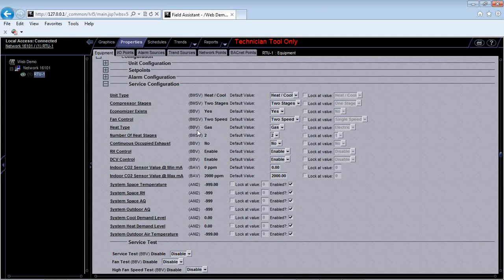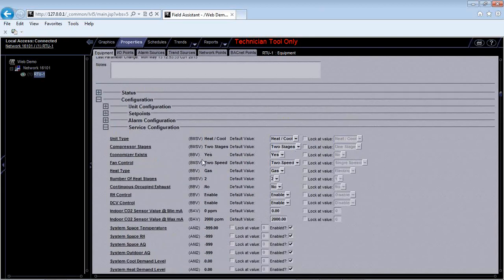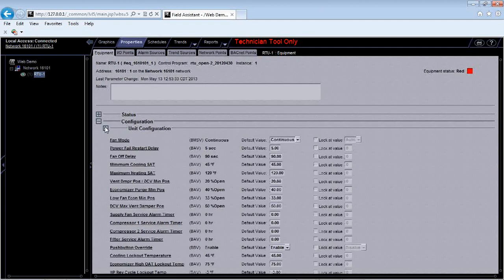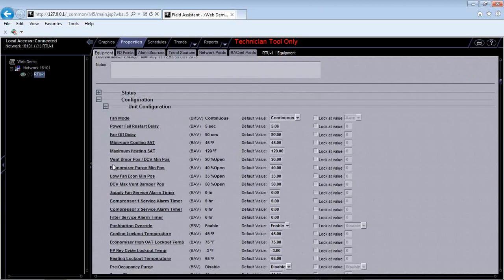And remember, we added an economizer. Once you make this change on this table, it's actually going to give you another set point on this unit configuration table, right? Because now we have economizer on here. You can see we got a couple more. So what we got was the DCV min position or the vent damper min position. This is my minimum economizer position. And then I have an economizer purge minimum position, a low stage fan economizer position, and a demand control ventilation max position. So those auto-generated once I put the economizer in the configuration mode. So you would want to adjust these set points to whatever you want locally on there.